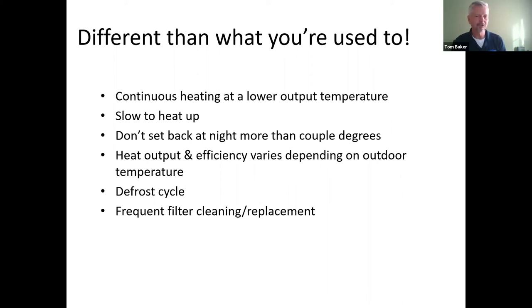And then the last thing is, it's important on your furnace to replace your filter every 3 months. It's critical on a heat pump system to replace the filter in the air handler or your furnace. When that gets clogged and the fan can't push enough air across the indoor coil, it can cause all kinds of problems. So we emphasize that when we install. We set people up, if they want us to, on automatic shipments for filters so that they don't forget. But that is really important. It's kind of like having an expensive car. You've got to take care of it. You can't neglect it and expect it to continue running great. All right.